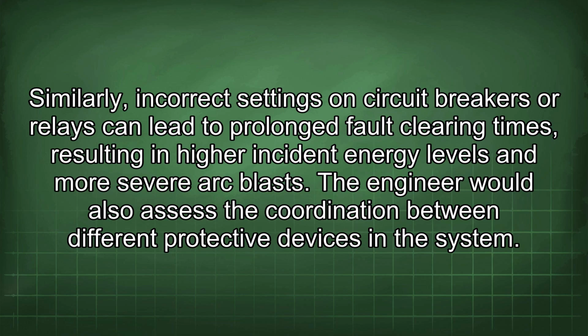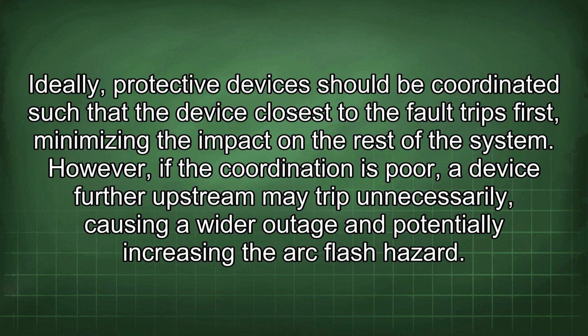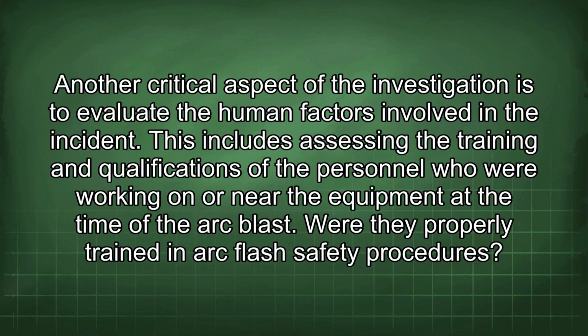The engineer would also assess the coordination between different protective devices in the system. Ideally, protective devices should be coordinated such that the device closest to the fault trips first, minimizing the impact on the rest of the system. However, if the coordination is poor, a device further upstream may trip unnecessarily, causing a wider outage and potentially increasing the arc flash hazard. Another critical aspect of the investigation is to evaluate the human factors involved in the incident.